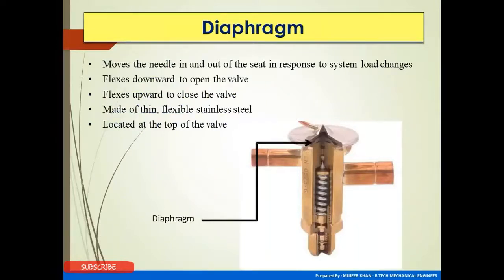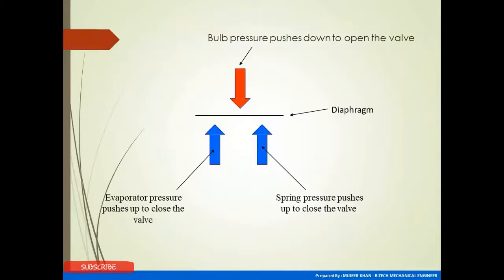The diaphragm moves the needle in and out of the seat in response to system load changes. These springs act as closing and opening mechanisms for the refrigerant. The bulb pressure pushes down on the diaphragm, while the spring and spring isolator push up to close the valve. Evaporator pressure also pushes to close the valve.